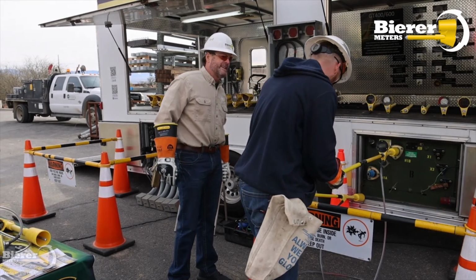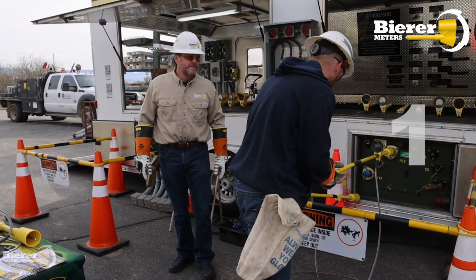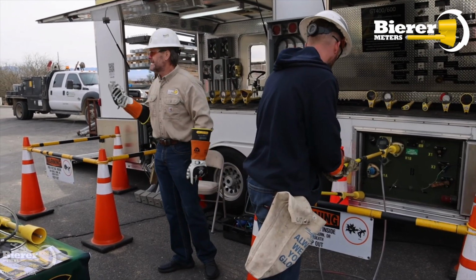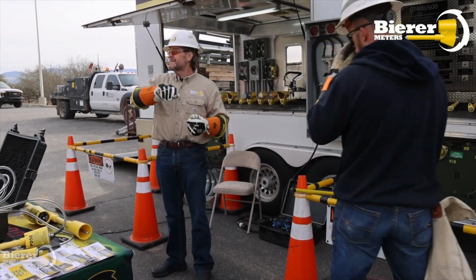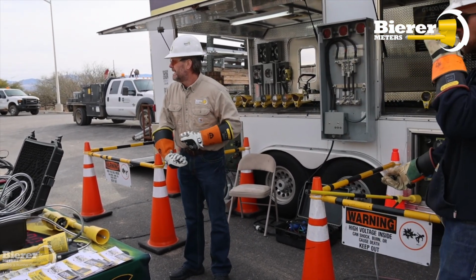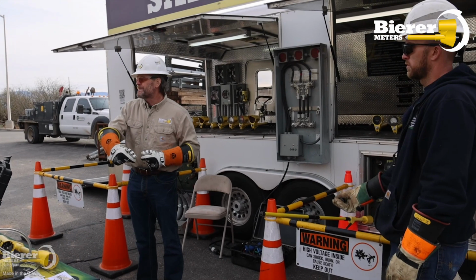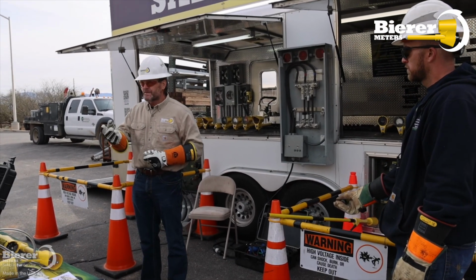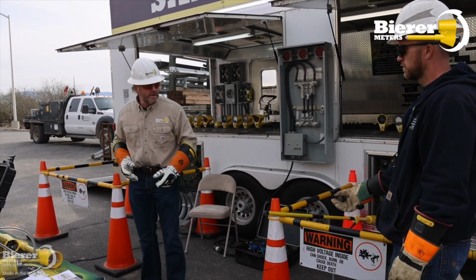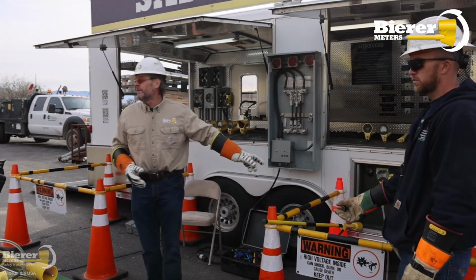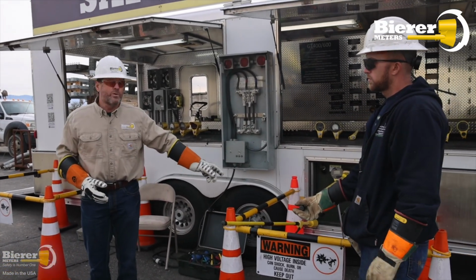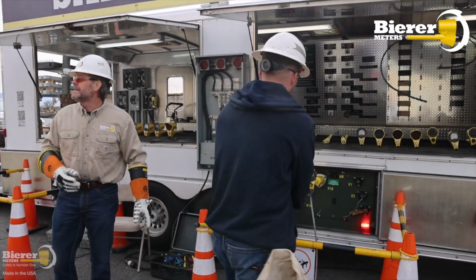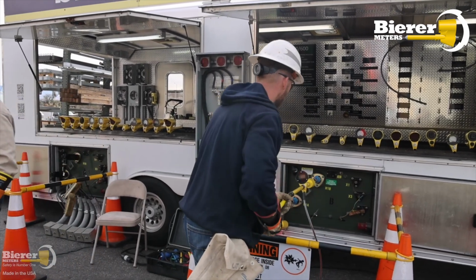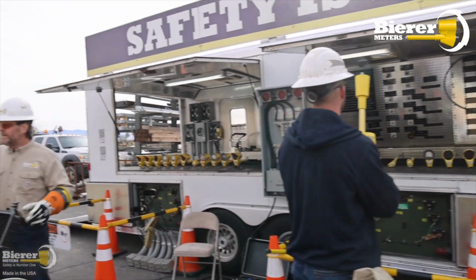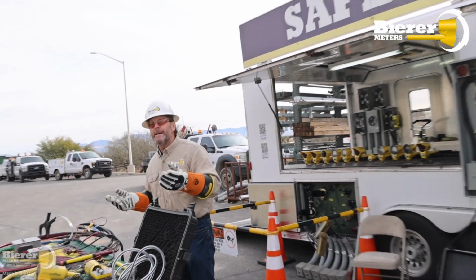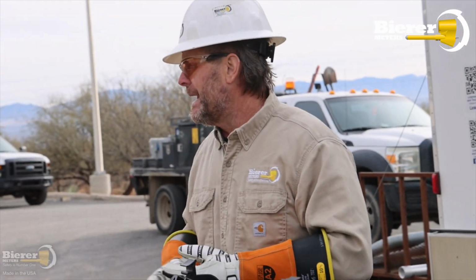Okay, what do you see? It says 1. The reason why it says 1 is because Dylan has the tool in the wrong setting. He's in the up to 2,000 V, which is going to be for your secondary type work. But we're on some primary overhead, so he needs to take it to 25 kV. All right, it doesn't hurt the tool. If you have our tools in the wrong position and use it, they just give you a funky reading. Just remember that, all right?